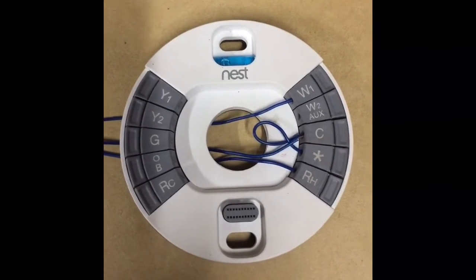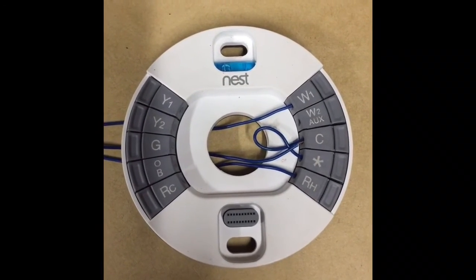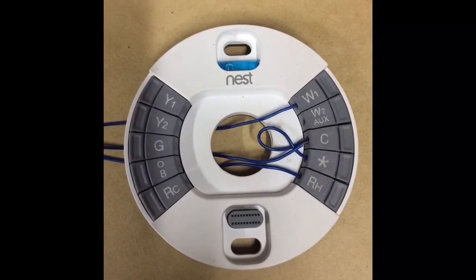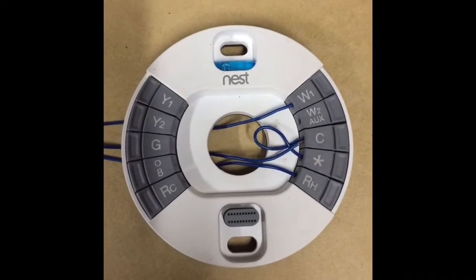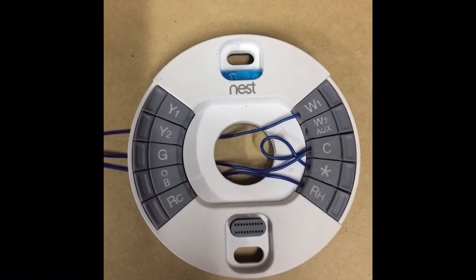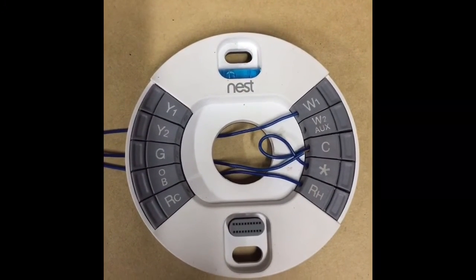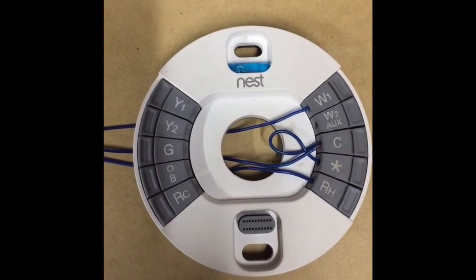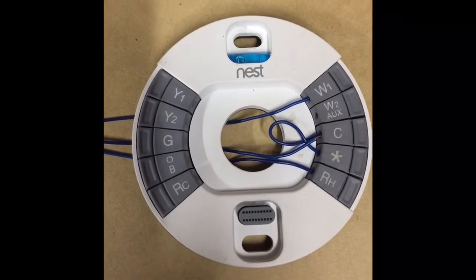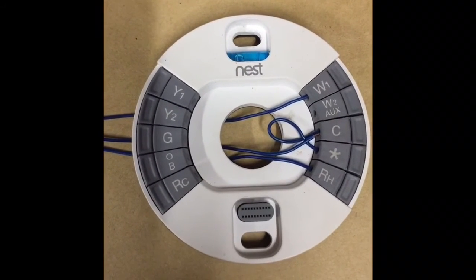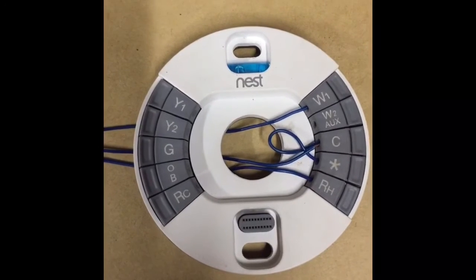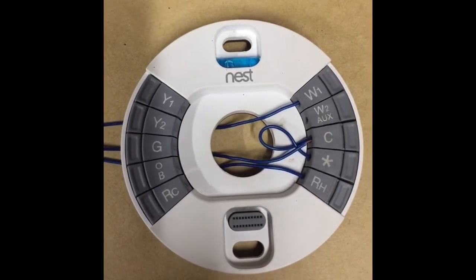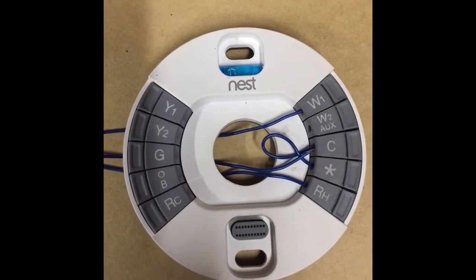For RH, we connect a multimeter probe up to the earth on a power point nearby, or an extension lead if you need to, and then we put the other probe on the wire, trying to establish which one has got 24 volts on it. The one with 24 volts goes into RH, the other one goes into W1. So that's the two wires on the wall from the existing thermostat worked out.